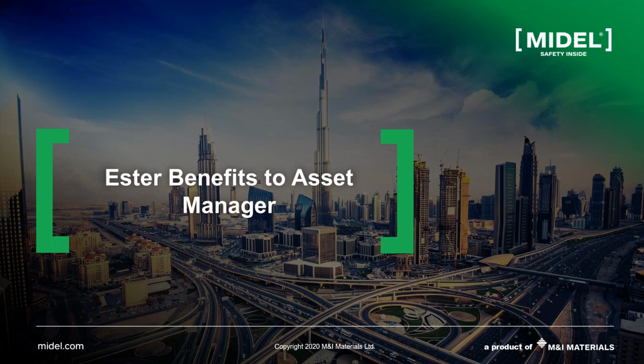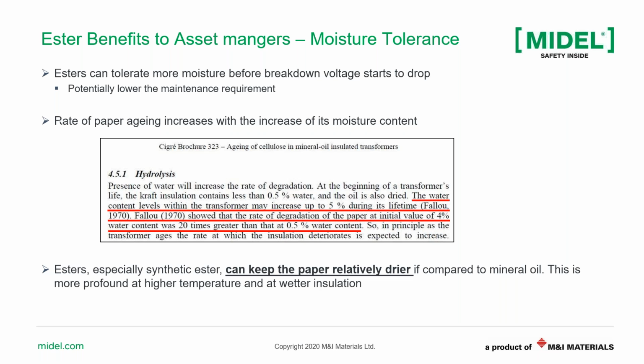And really, as I say, the time is running out, and so we are only touching very basically on this. I want to remind you here, before going into this, that esters, as I mentioned, have a different chemical structure compared to mineral oil, and so they can tolerate high moisture content without reducing the breakdown voltage. Now, for asset managers, what we are concerned with is when our assets will fail, and how we can devise replacement strategies, or if we can really extend the life of our assets without buying new ones. And so esters, because they can tolerate more moisture, can aid in reduced maintenance periods to go check wet transformers and sending your engineers.